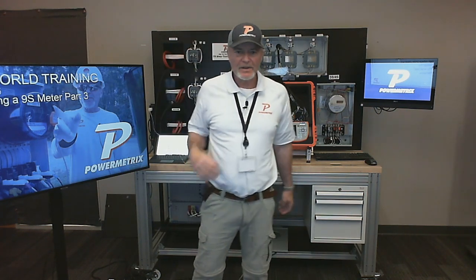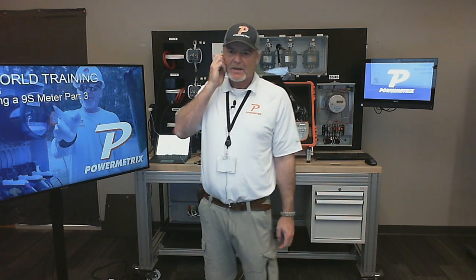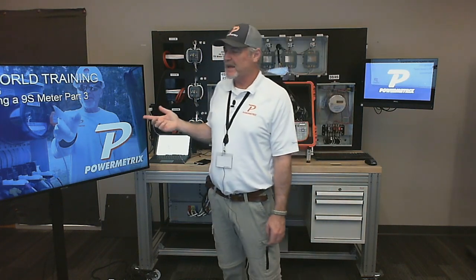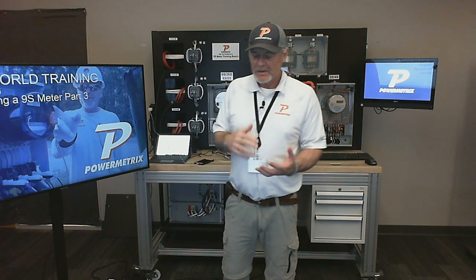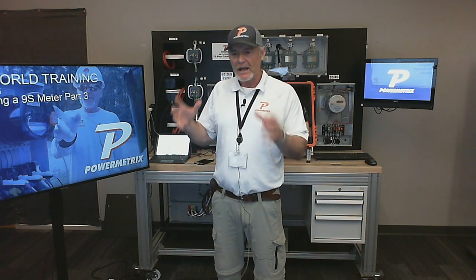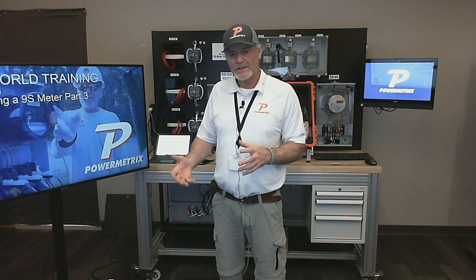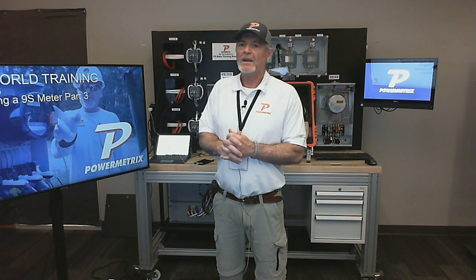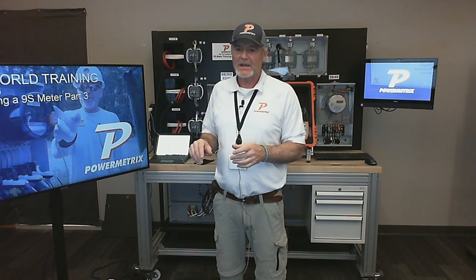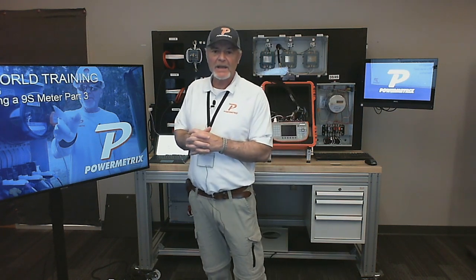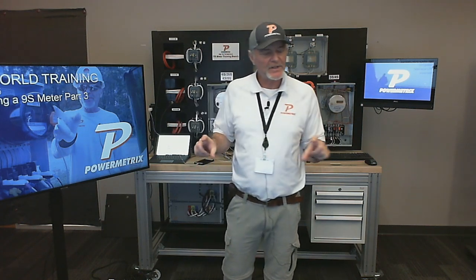So that's what we're going to do today. There's the agenda. Leading up to this, talking about this 9S site we went to, we showed up, did our inspection, looked at the pole, the conduits on the pole, transformers on top of the pole, and we noticed some washout at the base of the pole. We also noticed some arcing in the back of the meter can. Looked like they had probably changed out the test switch in there because it was different than the ones we had seen earlier.